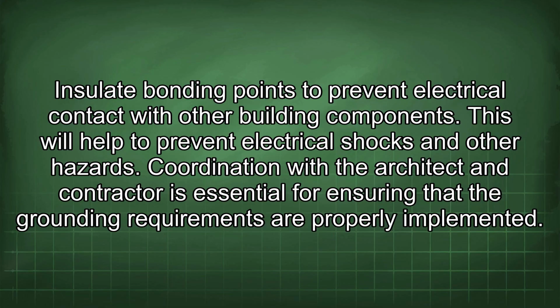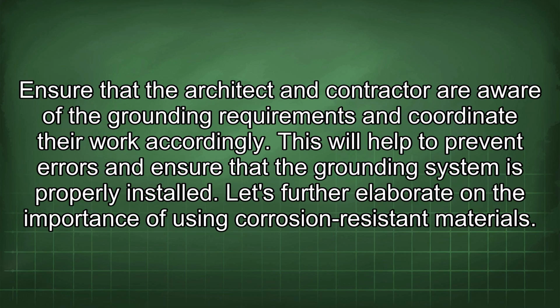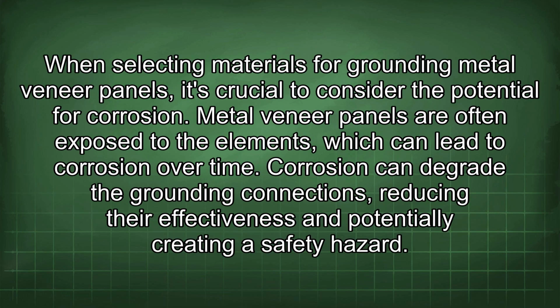Coordination with the architect and contractor is essential for ensuring that the grounding requirements are properly implemented. Ensure that the architect and contractor are aware of the grounding requirements and coordinate their work accordingly. This will help to prevent errors and ensure that the grounding system is properly installed. Let's further elaborate on the importance of using corrosion-resistant materials. When selecting materials for grounding metal veneer panels, it's crucial to consider the potential for corrosion. Metal veneer panels are often exposed to the elements, which can lead to corrosion over time. Corrosion can degrade the grounding connections, reducing their effectiveness and potentially creating a safety hazard.